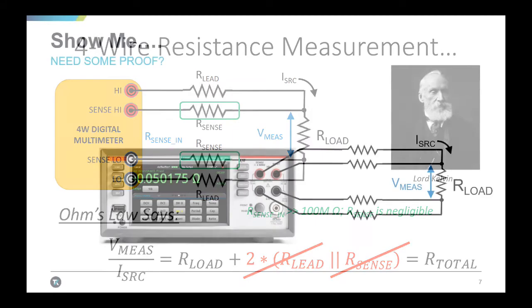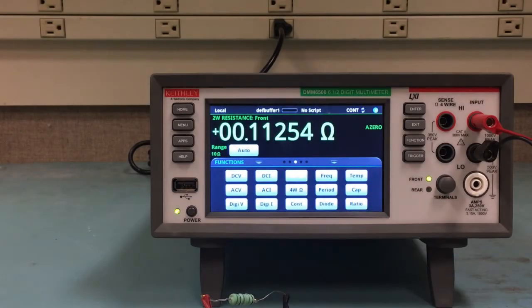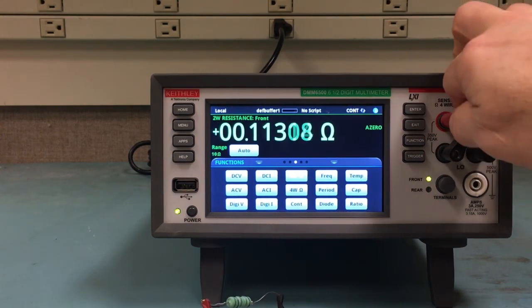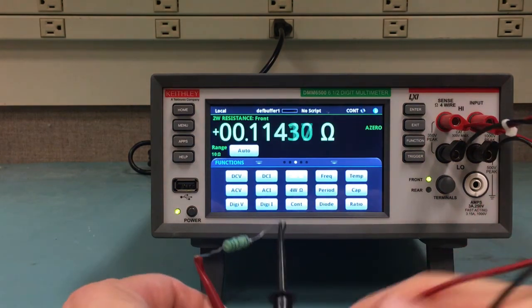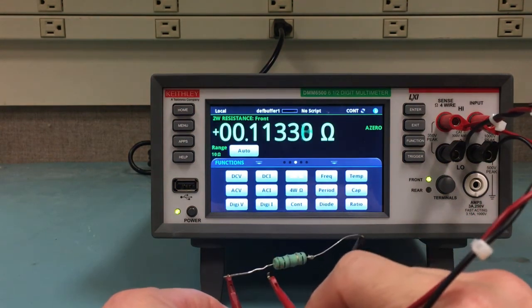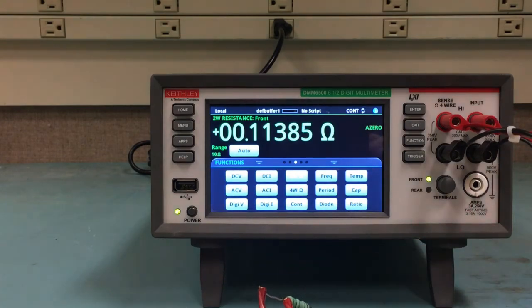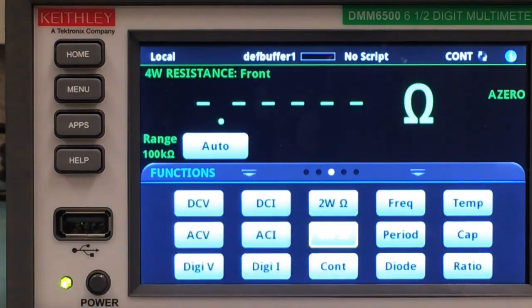Let's perform the four-wire measurement. The first step is to connect my second set of leads to the sense inputs on the front of the DMM 6500. I then use those leads to clip very closely to the resistive body of my device under test. I can then change my measurement function to four-wire.